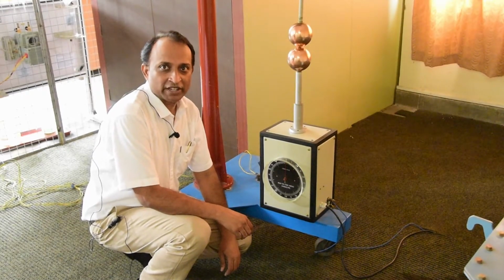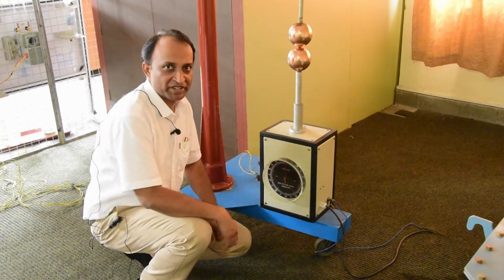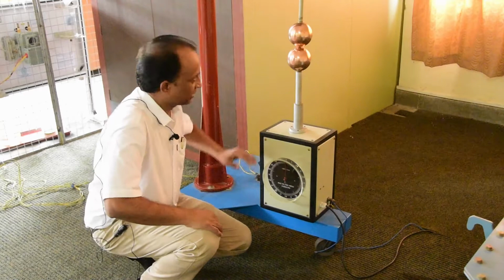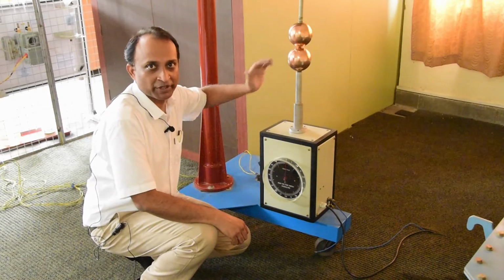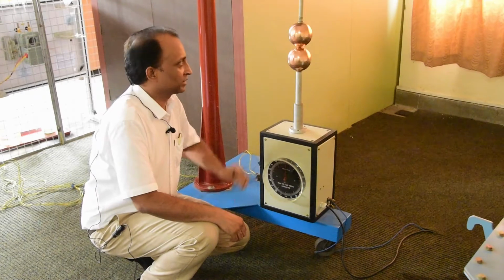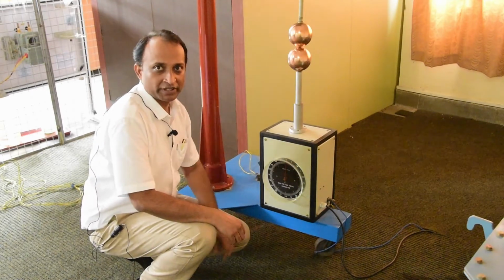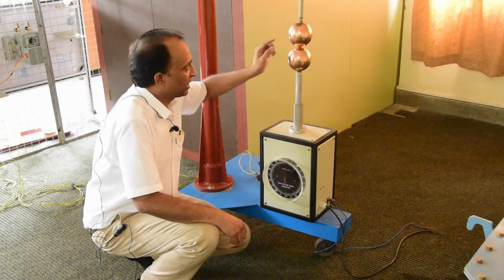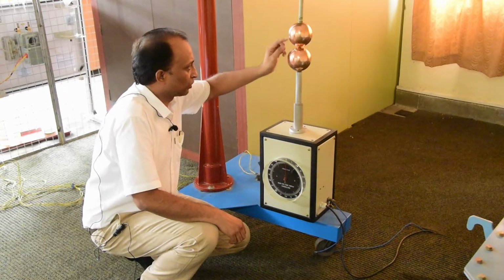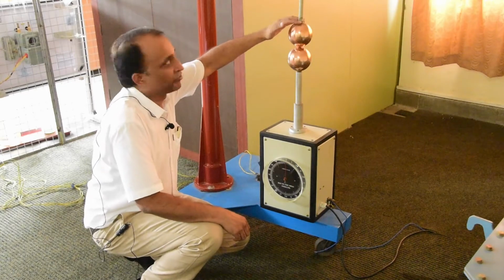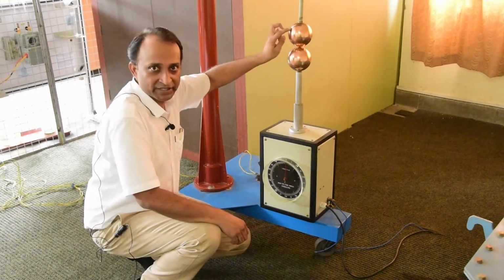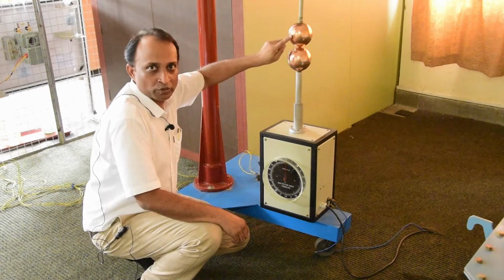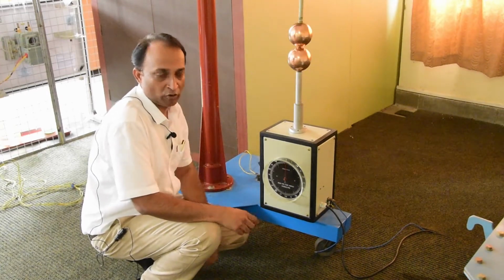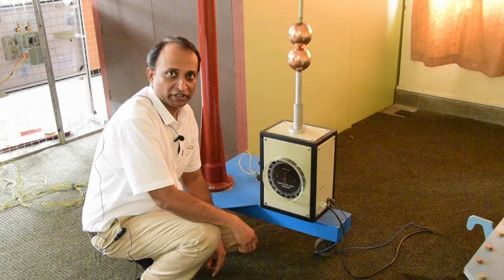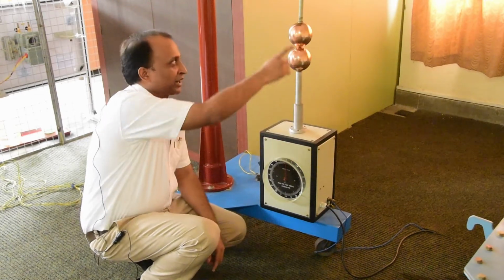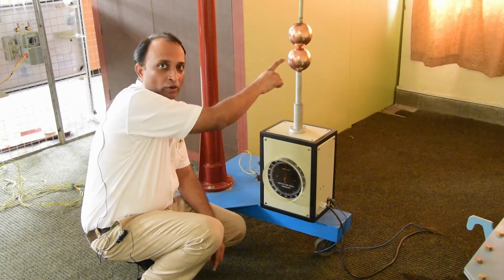Let us check with the sphere gap assembly. Already I have told that there are two spherical electrodes. The diameter of these individual electrodes is 10 centimeters. The upper electrode is fixed to an insulated stand, and it is connected to the high voltage terminal output coming from the cascade transformer that we have seen earlier. So the high voltage output is connected to the upper electrode.